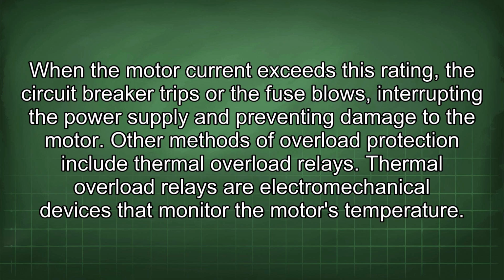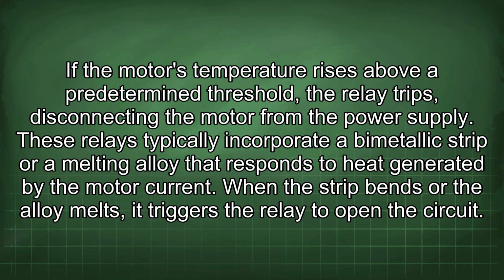Other methods of overload protection include thermal overload relays. Thermal overload relays are electromechanical devices that monitor the motor's temperature. If the motor's temperature rises above a predetermined threshold, the relay trips, disconnecting the motor from the power supply. These relays typically incorporate a bimetallic strip or a melting alloy that responds to heat generated by the motor current. When the strip bends or the alloy melts, it triggers the relay to open the circuit.